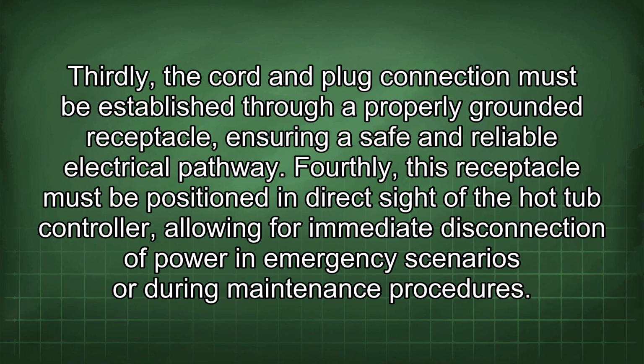Thirdly, the cord and plug connection must be established through a properly grounded receptacle, ensuring a safe and reliable electrical pathway. Fourthly, this receptacle must be positioned in direct sight of the hot tub controller, allowing for immediate disconnection of power in emergency scenarios or during maintenance procedures.